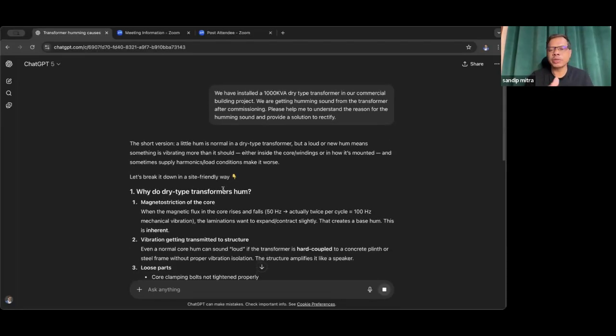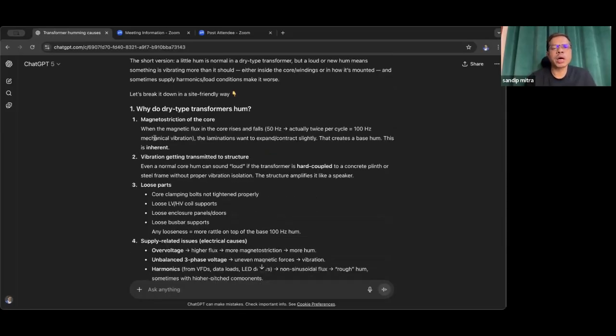So I will read out what is mentioned by ChatGPT. A little hum is normal in a dry type transformer, but a loud or new hum means something is vibrating more than it should, either inside the core or windings or in how it's mounted. And sometimes supply harmonics or load conditions make it worse. So let's break it down this way. Why do dry type transformers hum? These are the reasons mentioned. Magnetostriction of the core: when the magnetic flux in the core rises and falls, at 50 hertz the actual frequency is twice per cycle, equal to 100 hertz mechanical vibration. The laminations want to expand or contract slightly. That creates a bass hum.